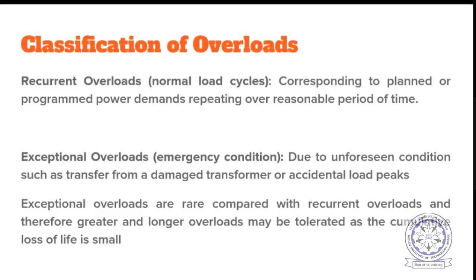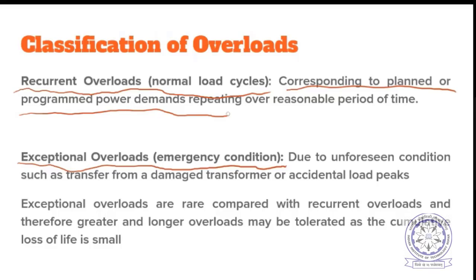The overloading is classified as follows. There are two types of overloads: recurrent overloads and exceptional overloads or emergency conditions. Recurrent overloads are defined as corresponding to planned or programmed power demands repeating over a reasonable period of time, for example a 24-hour period. So every day it repeats for a certain amount of time. It is a pre-planned or even programmed power demand. So every day for 1 or 2 hours, it exceeds the rated load of the transformer. Such loads are called recurrent overloads, or due to normal load cycles.